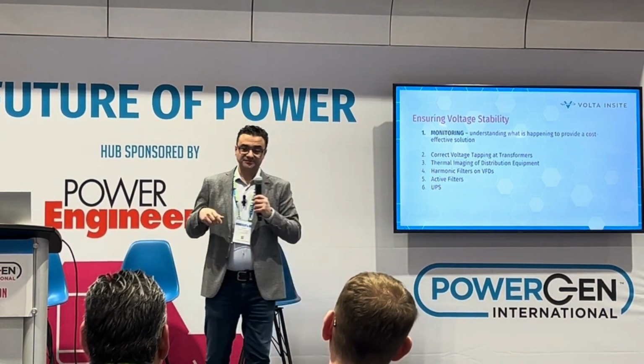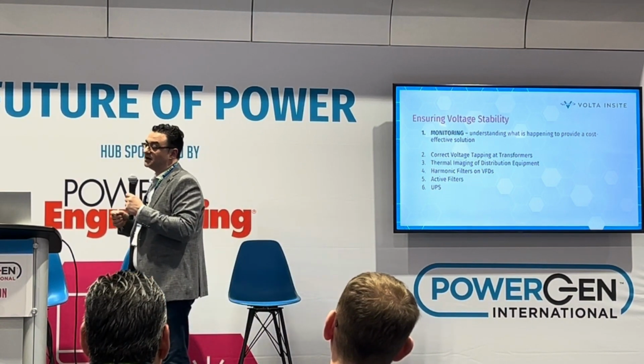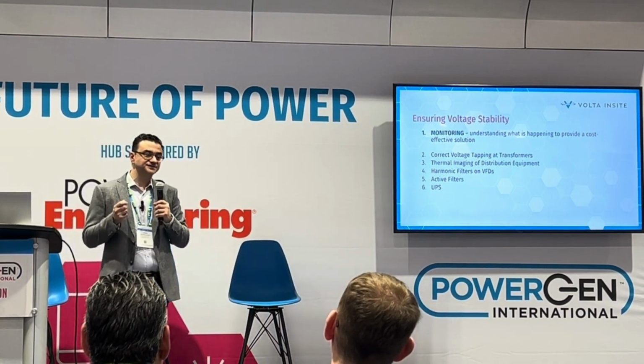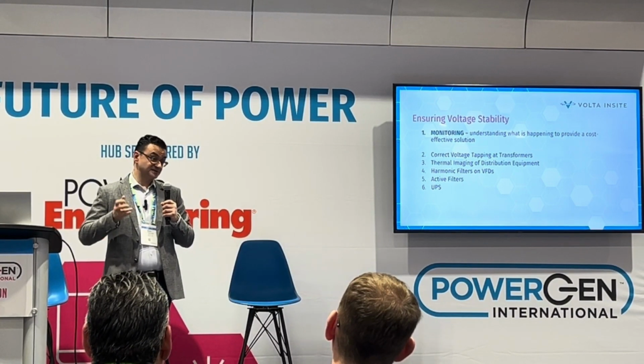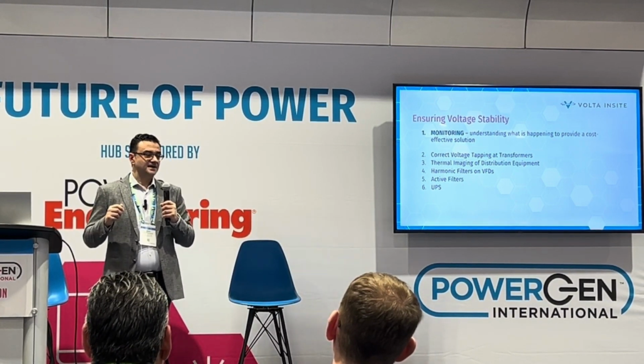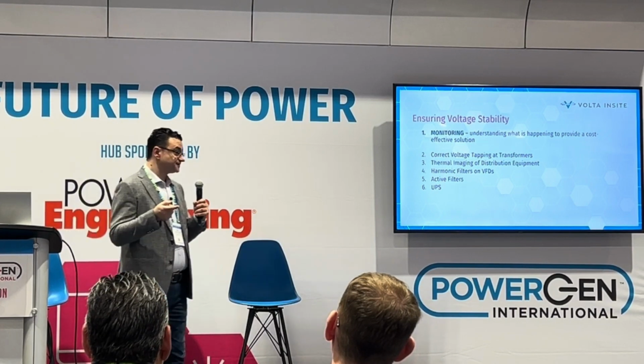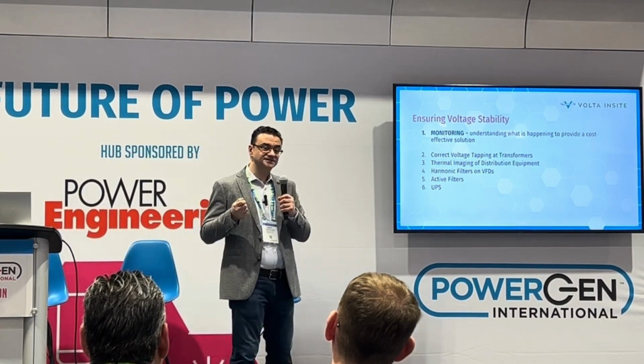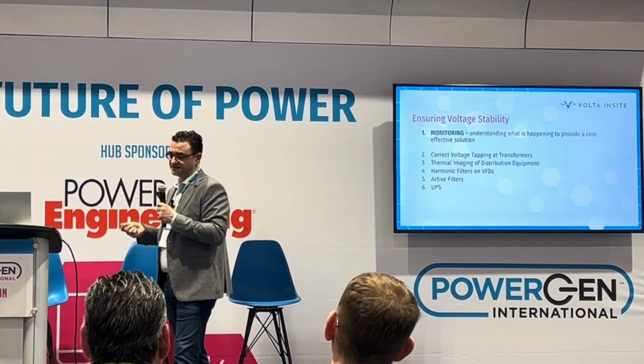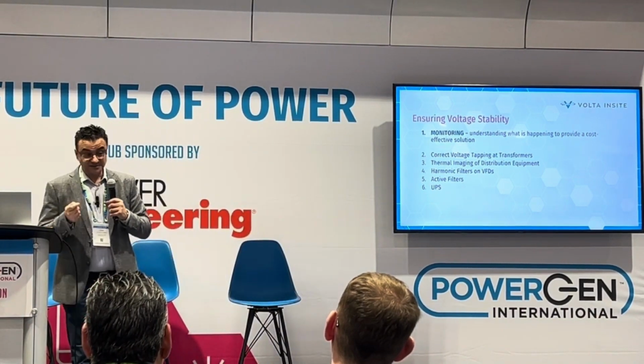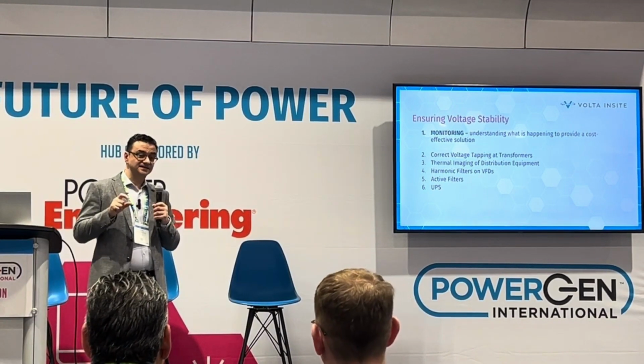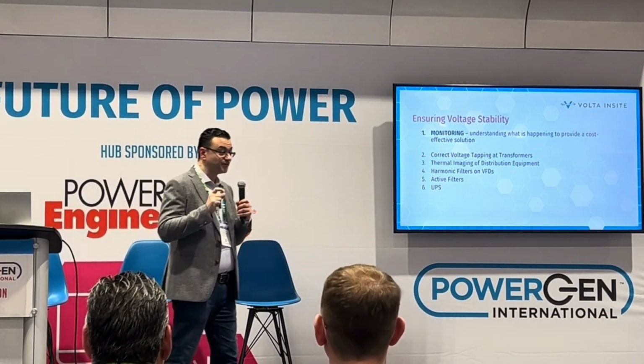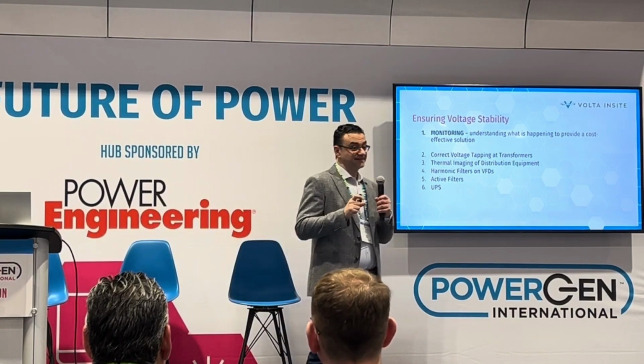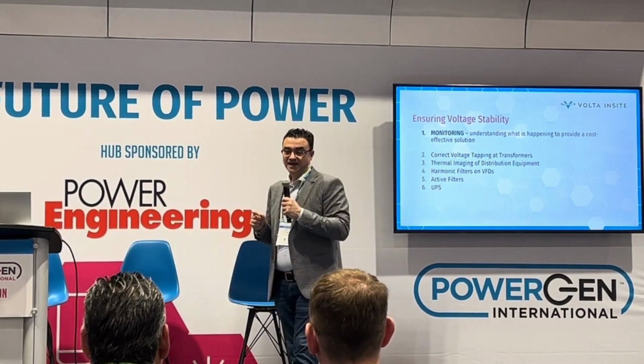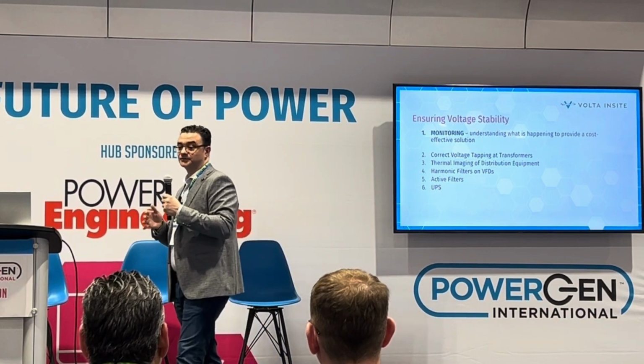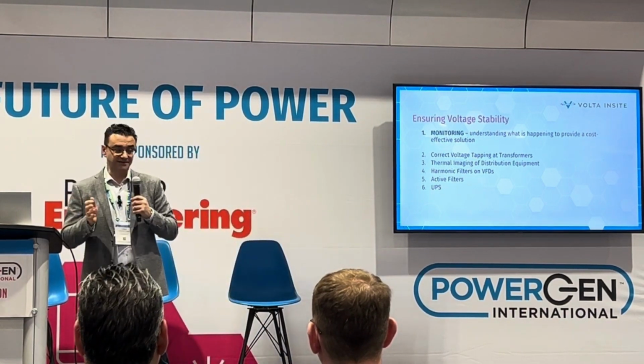So we did some startups, we did some captures, and what we noticed was on the startup, there were significant voltage fluctuations that the generator was ultimately producing. And because of the voltage fluctuations, the VFD was going into under voltage protection and kicking out. So we did some more testing, and it turns out that the sense circuit of the voltage regulator for the generator was accumulating sense error and was effectively turning off the voltage regulation, the field current for the generator.